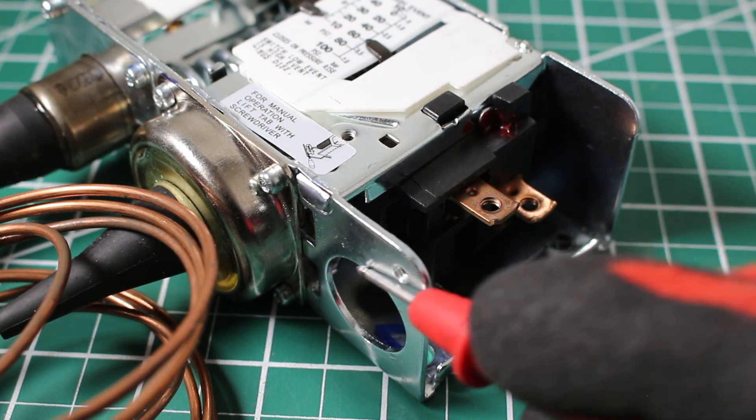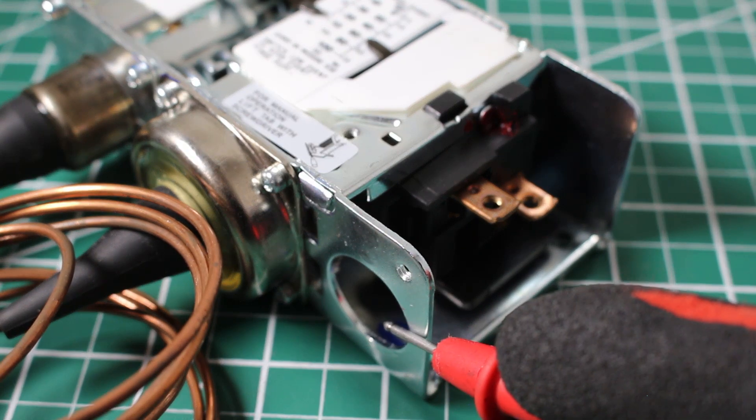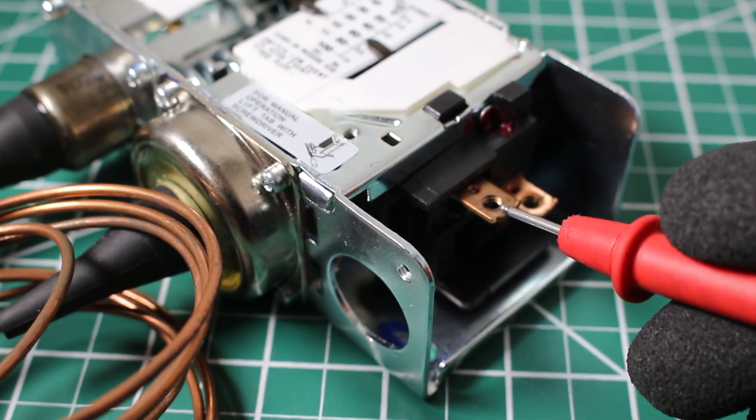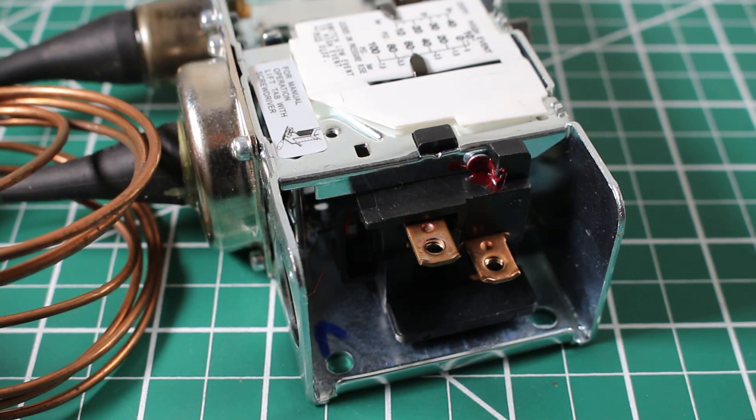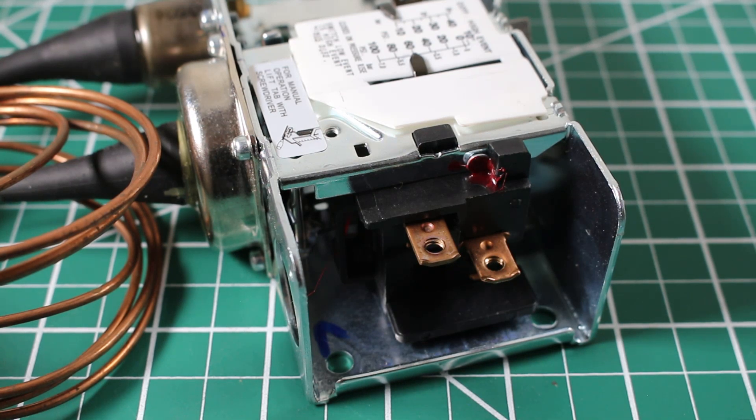If we look here, we have a knockout where we can bring in our electrical wires. And here we have two conductors. A dual pressure control operates with the principles of a switch. And as you can see, we have two conductors. You also will come across some with four conductors. Depending on the model, you will find a single pole single throw switch or a double pole single throw switch.